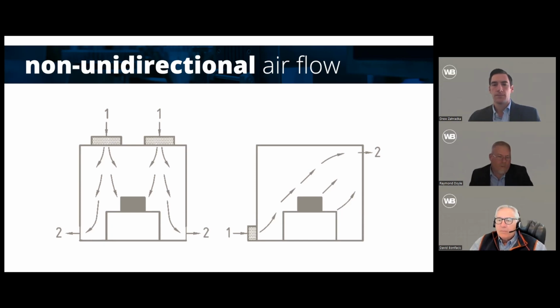So, in most cases in the world of biotech, until you get up into the ranges beyond ISO 6 and you get into the EU classes, into the B and C ranges, where you have to have a true unidirectional flow and get better airflows and better control over the airflow. So depending on the industry, Dave, you get different applications, and that's really what it comes down to: how specific does the airflow need to be at a specific point in the space, whether that's horizontally or vertically, to either protect the equipment or the science that's being performed.